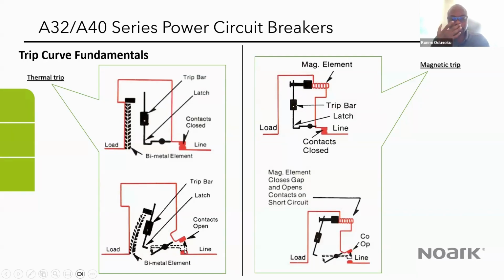And that's what happens for the thermal protection. For the magnetic protection, it's just a wire that is wound around some kind of plunger. So when the magnitude of the current reaches a particular threshold, it's going to force the trip bar to release, and then you're going to have the contacts opening up. That used to be the traditional way that circuit breakers were designed.